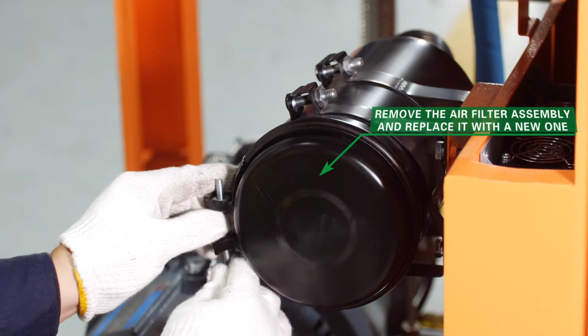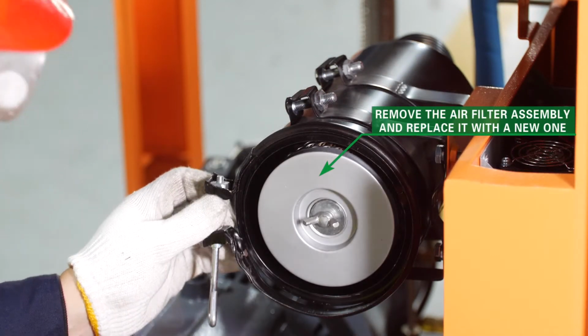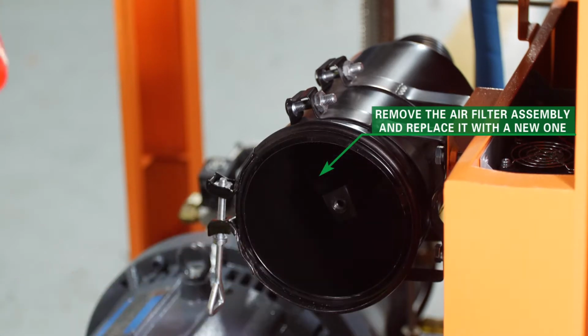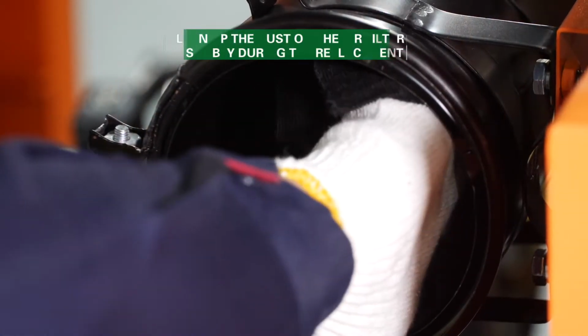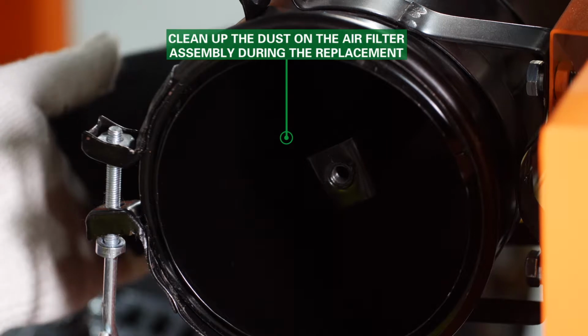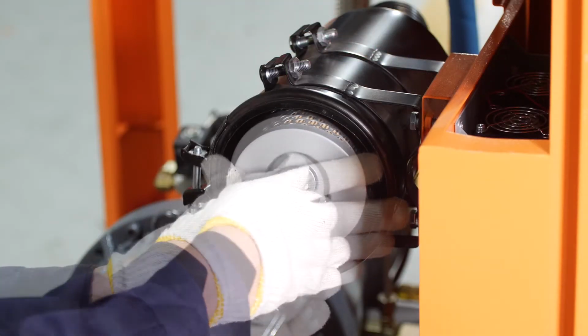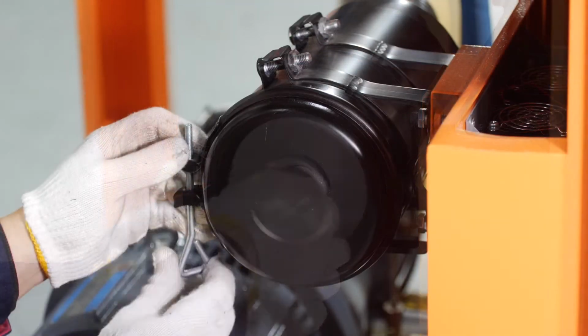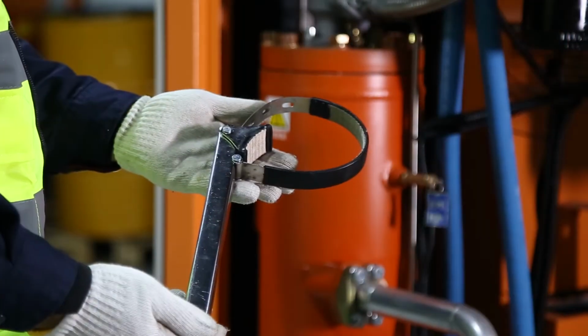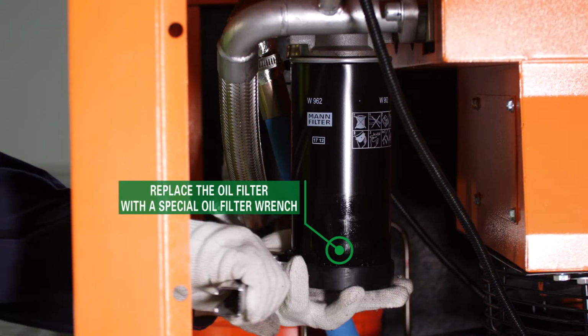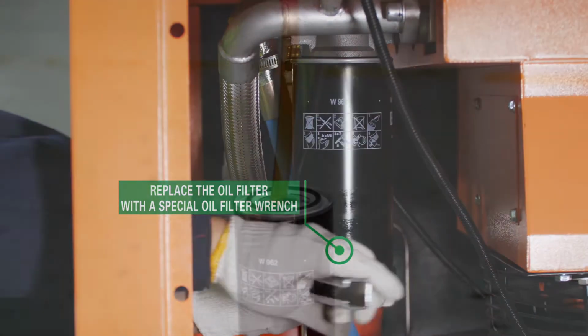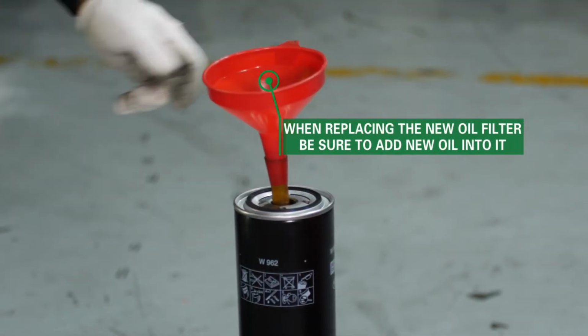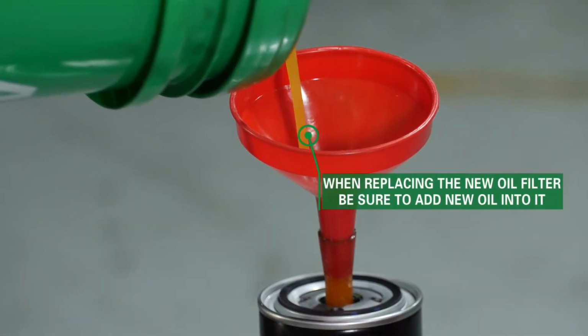Remove the air filter assembly and replace it with a new one. Clean up the dust on the air filter assembly during the replacement. Replace the oil filter with a special oil filter wrench. When replacing the new oil filter, be sure to add new oil into it.